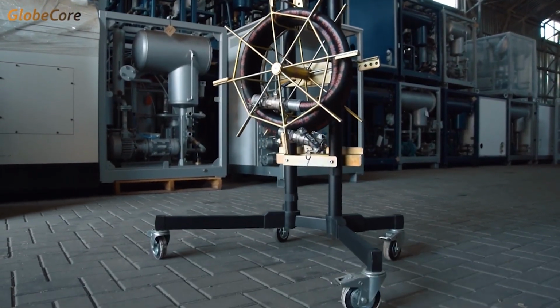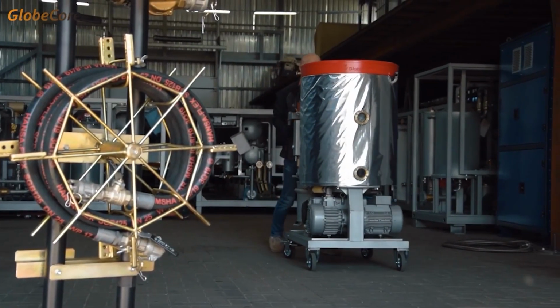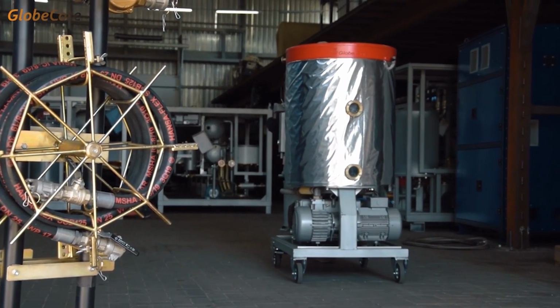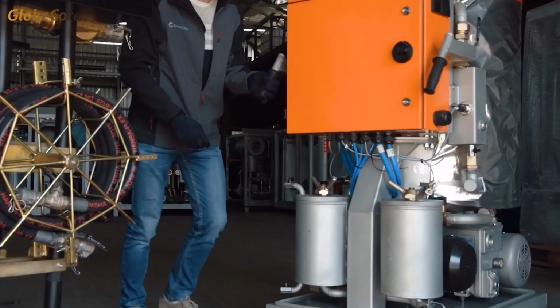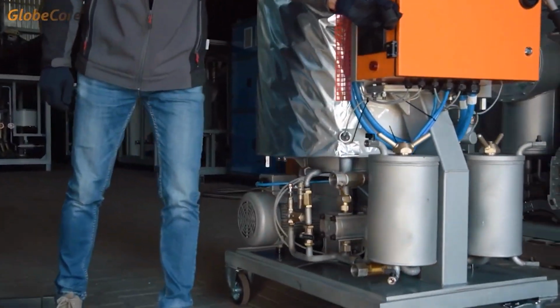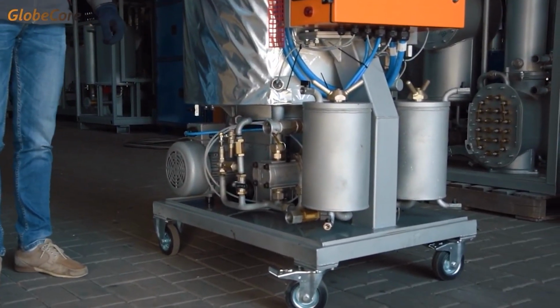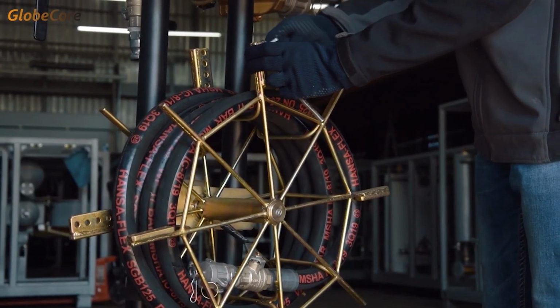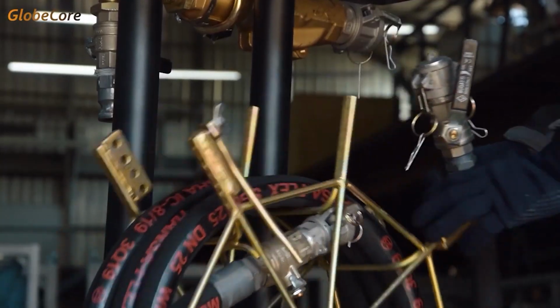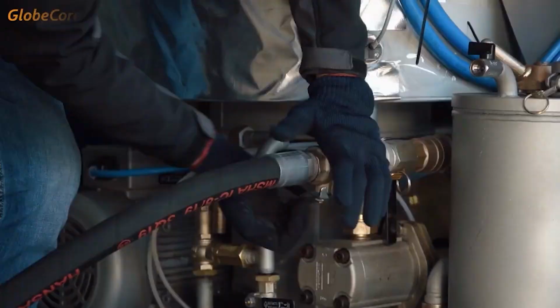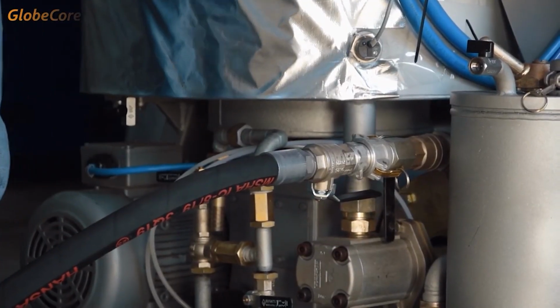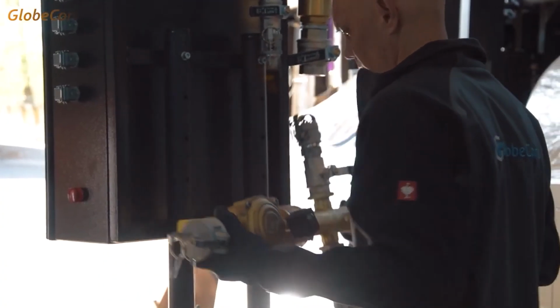The TSS system may be employed not only with Globecore machines, but also with machines built by other manufacturers, after engineering study and adaptation of the system. The TSS controls the operation and parameters of a transformer during oil purification, degassing or regeneration. This ensures safe operation on an energized transformer.